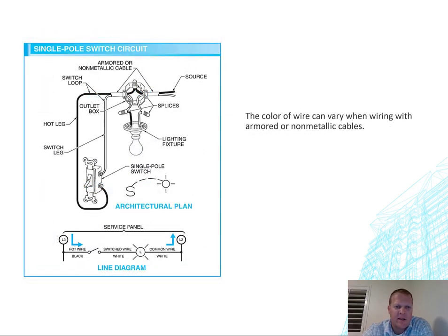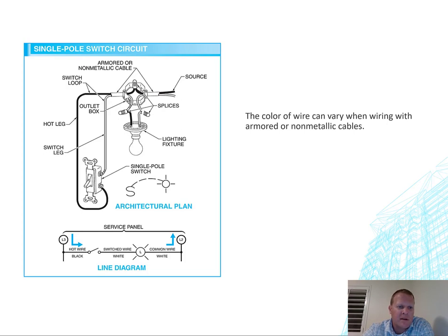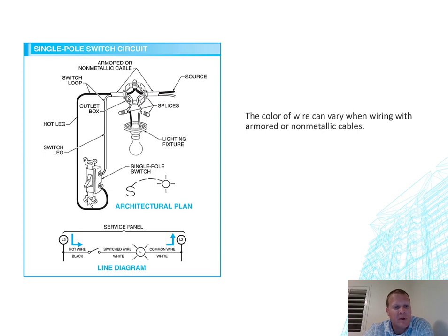We went over this last time but didn't spend a lot of time on it. The last lecture went through all this in EMT — electrical metallic tubing. But we also have armored or non-metallic cable, and they're showing the wiring here and how it could be done. You have the source, and notice the black wire isn't immediately going to the light fixture. In this case, say the power source was over here in the room, and they want to put the light switch farther away from the power source. So you could run some armored cable — like MC or BX — or Romex and bring that through.